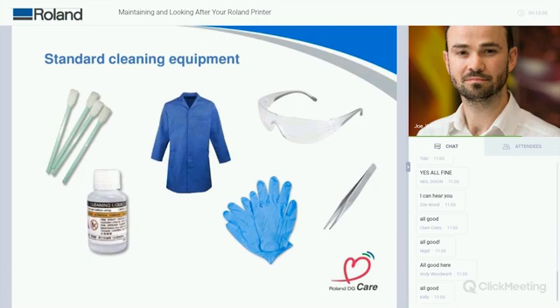So the first thing that you should be looking at is cleaning swabs. You will have got a pack of these with the machine, along with some of the cleaning liquid there. You can order these from your ink supplier, usually if you begin to run out. But these are going to be the main things you'll use as part of the cleaning. Ideally, you'll have a lab coat or some kind of coat to wear in order to cover your skin, as you don't want to risk getting any of this cleaning solution on your skin. If you do, clean it off immediately. The same goes for the gloves and goggles. They're there to protect you.